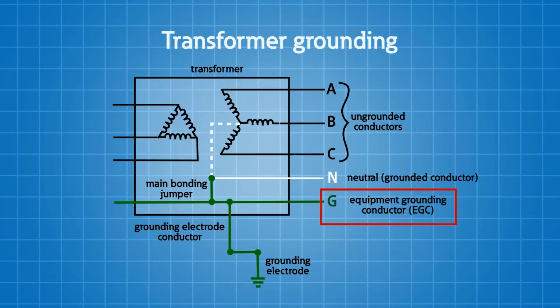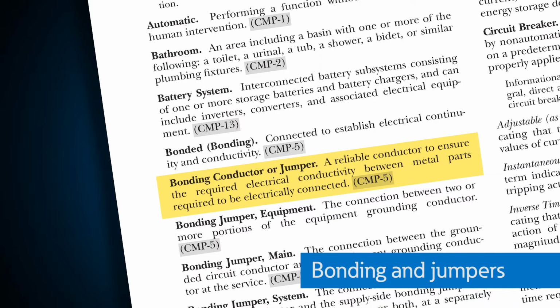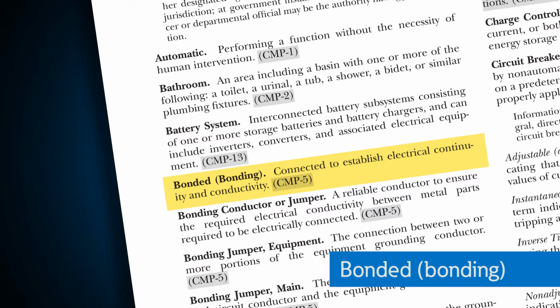That's a conductor that is used to connect the equipment or the grounded circuit of a wiring system to a grounding electrode or to the grounding electrode system. Now, bonding and jumpers. We're going to get into an area where we're pulling things together. We're talking about bonding, and the National Electrical Code defines bonded as connected to establish electrical continuity and conductivity. This is a very important term as we work throughout the power distribution system.